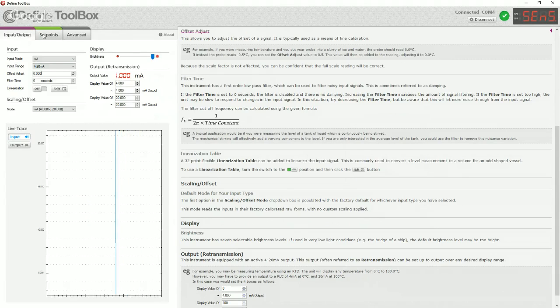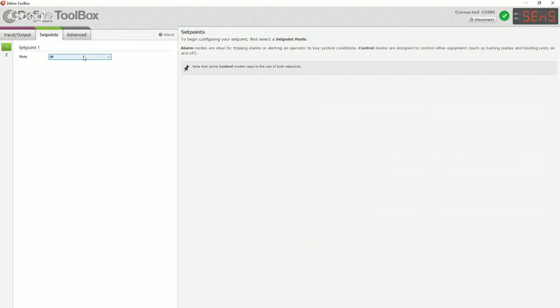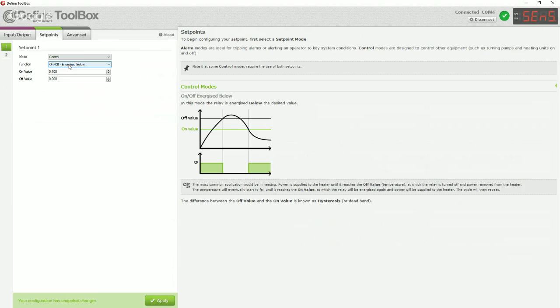So we click apply down the bottom. We can now go to configuring the relays. So if we were just going to use a very simple control mode, let's start with set point 1. So in this mode box, we can choose from control, alarm, and off. So I'll pick control. The second box there is function, which has got energized below, energized above, and then there's some more complicated pump alternation modes, which we'll use in a second, but let's start with a simple one. So let's say we're going to be energized below, because we want the pump to turn on when the water level drops below a certain limit.